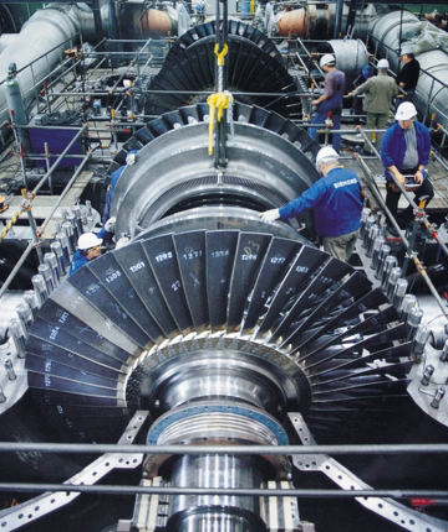The first supervisory control systems implemented consisted of a panel of lamps and switches at a central console near the controlled plant. The lamps provided feedback on the state of the plant, the data acquisition function, and the switches allowed adjustments to the plant to be made, the supervisory control function.